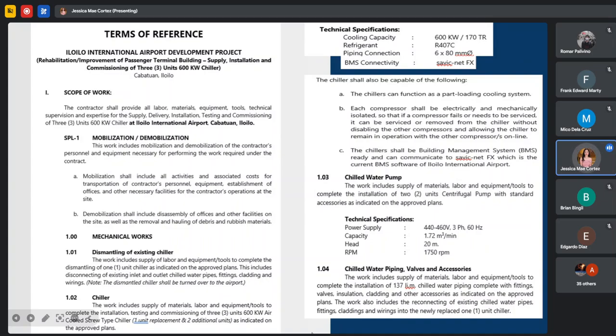The chiller shall also be capable of the following. A. The chillers can function as a part loading cooling system. B. Each compressor shall be electrically and mechanically isolated so that if the compressor fails or needs to be serviced, it can be serviced or removed from the chiller without disabling the other compressors, allowing the chiller to remain in operation with the other compressors online. Letter C. The chillers shall be BMS ready and can communicate to savic-net FX, which is the current BMS software of Iloilo International Airport. 1.03 chilled water pump.